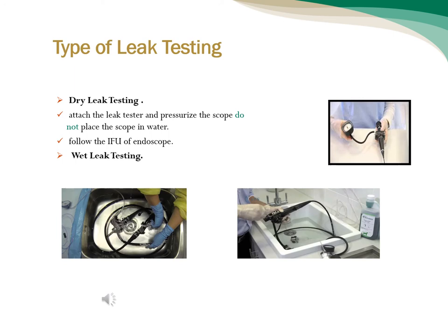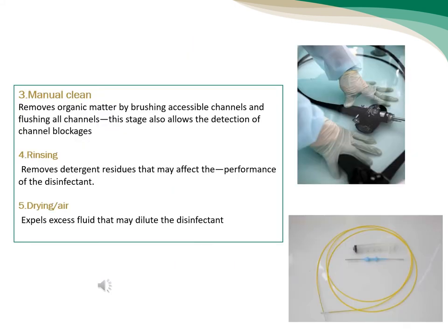Types of leak testing: dry leak testing and wet leak testing. Manual clean: remove organic matter by brushing accessible channels and flushing the channels. Rinsing removes detergent residue that may affect the performance of the disinfection. Drying expels fluids using air pressure.